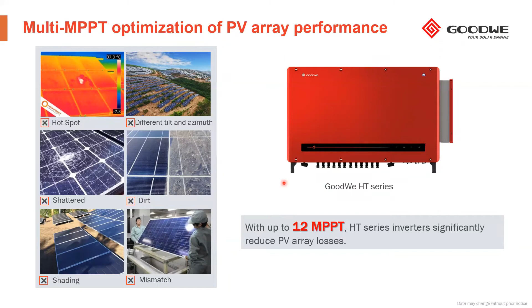And mismatch is quite common - this happens often when we combine different PV cell or PV module technologies. With an inverter with multi-MPP tracker technology, we can use different technologies, but always keeping the same technology per MPP tracker.